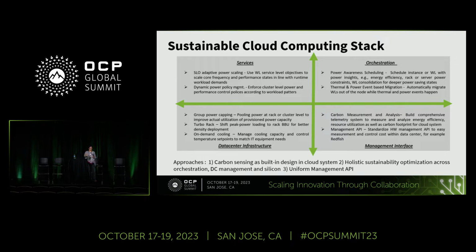Secondly, we are also dynamically doing power and performance management, dynamically adjusting the P and C states based on some predictive models. If, let's say, we have a customer who has a certain period of a day that the servers are not being used, they want to put those servers in sleep states. So we will use this solution to put those in sleep states and wake them up prior to when they need them. So that's the dynamic PC state optimization.